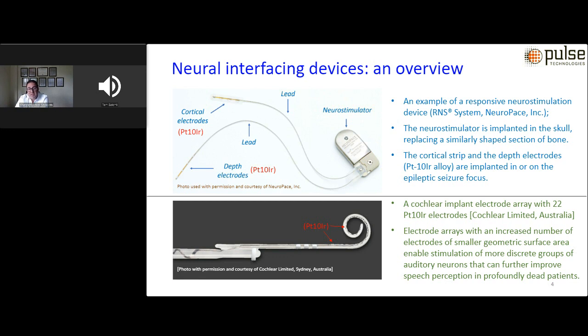So the majority of these devices consist of essentially three major components. The IPG, which is the implantable pulse generator, or in some cases referred to as a neurostimulator, that contains the battery and electronics and the circuitry of the device, which essentially is the brain or the CPU of the device. Electrodes or microelectrode arrays that are responsible for sensing and recording of neurological or cardiac activity, and leads that basically bridge between the pulse generator and the electrodes or microelectrode arrays. Some examples are shown here on the slides.